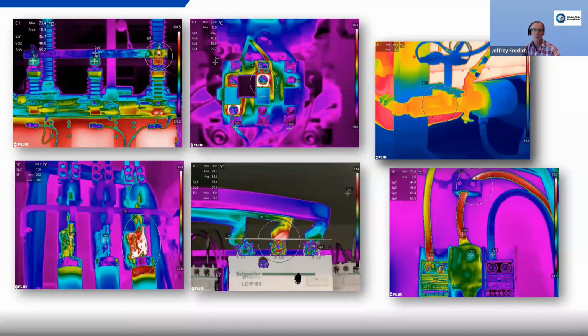In the middle, I've used some software techniques on this. Normally, you're going to use an iron palette for electrical. I've done this for effect, for a little bit more visual appearance. I've used what's known as thermal fusion here. These cameras have the ability to do both thermal and digital, so you've got the two overlaying each other, and you can see the digital picture of the breaker. And this is at a cocoa plant. The B phase has a deteriorated, bad lug connection that's in need of clean and tightening.